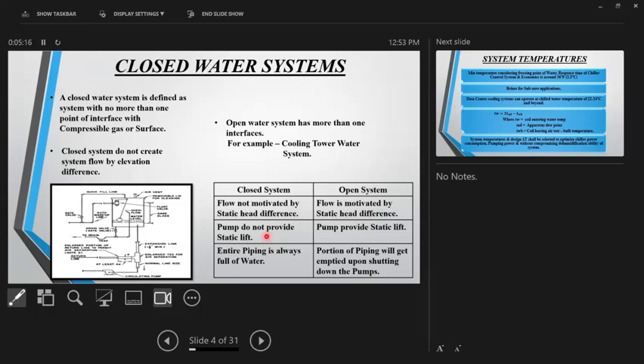Another difference is that in closed water systems, the pump is really not required to provide any static lift. You can talk about 200 meter tall, 300 meter tall, the pump is really not bothered. It is not required to provide any static lift. What it needs to do is only respond to frictional drops. Whereas in open systems, obviously you are required to provide a static lift. In a cooling tower circuit, the static lift is nothing but the height of the cooling tower, right? Because there are two open surfaces through which the water is required to be lifted. So in open systems, you need to consider the static lift.